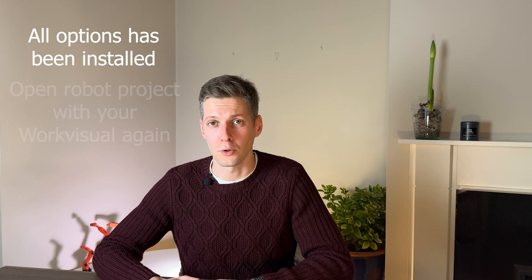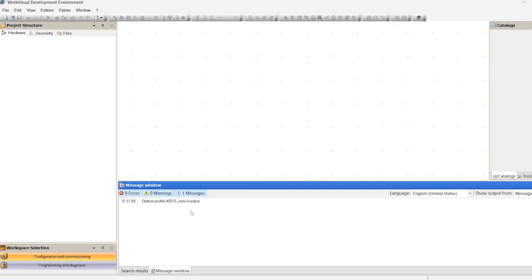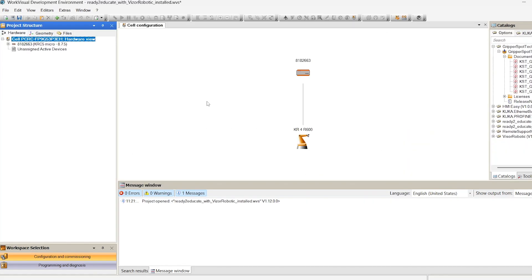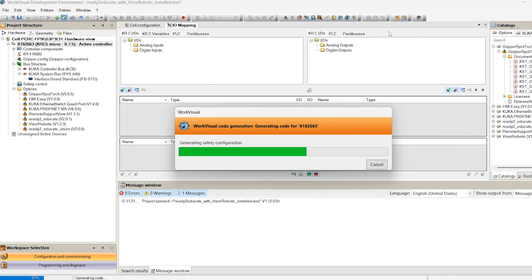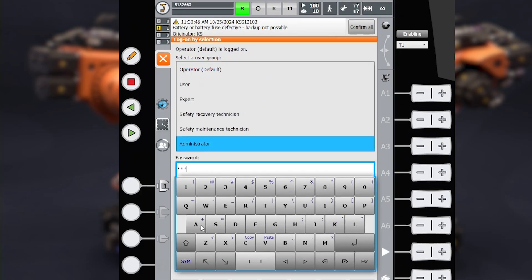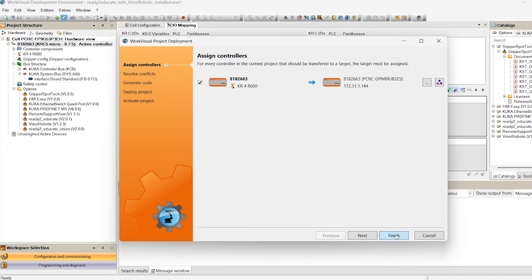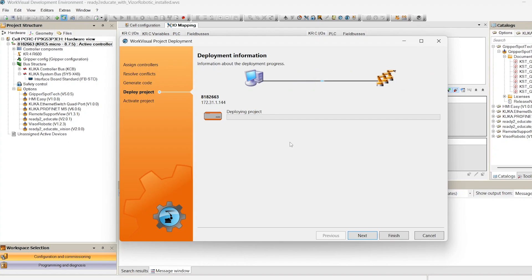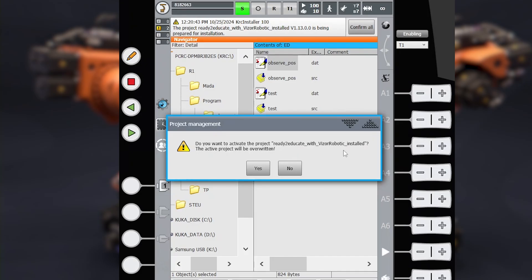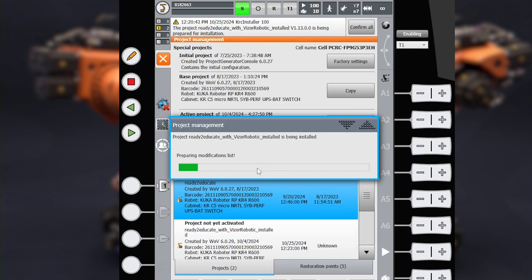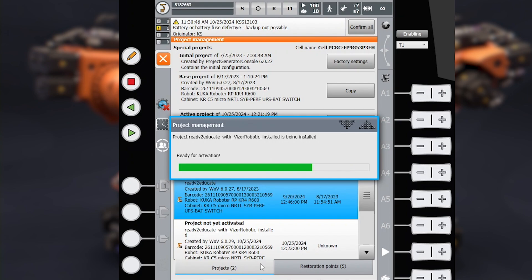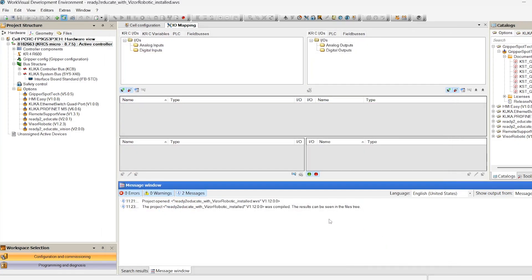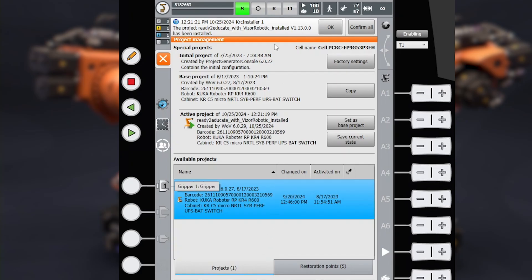When all the required KUKA options are installed into your WorkVisual, let's open the project one more time. Now I can't see any warning messages about missing packages. I will compile the project without any changes and deploy it from my prepared WorkVisual into the robot controller. Administrator mode and some manipulations on the SmartPad side are required during the activation. Activate it — no errors on the WorkVisual side, no errors on the robot controller side. Congratulations, job's done!